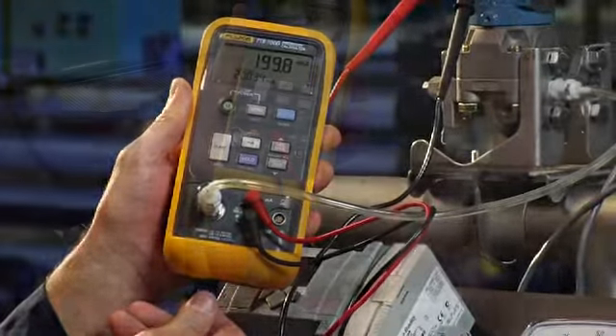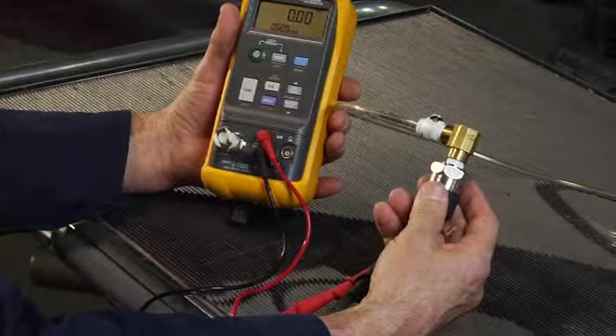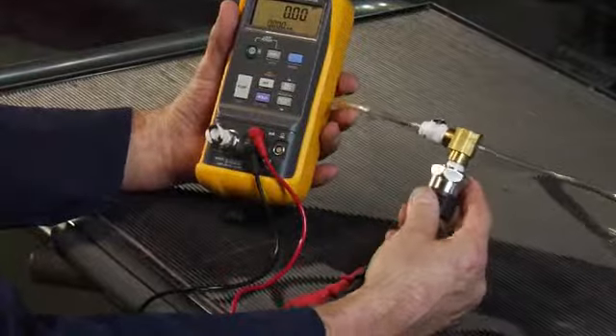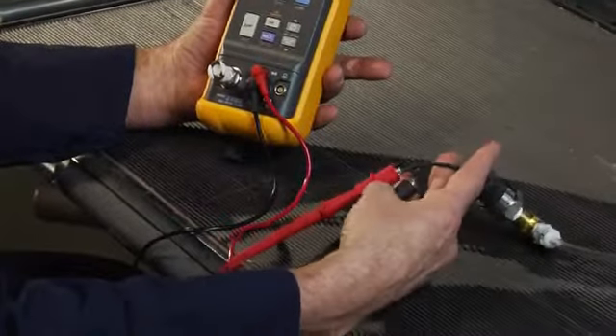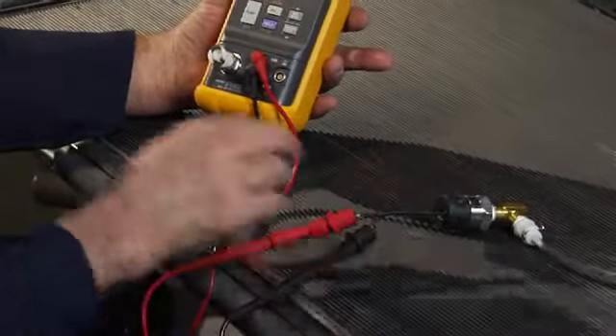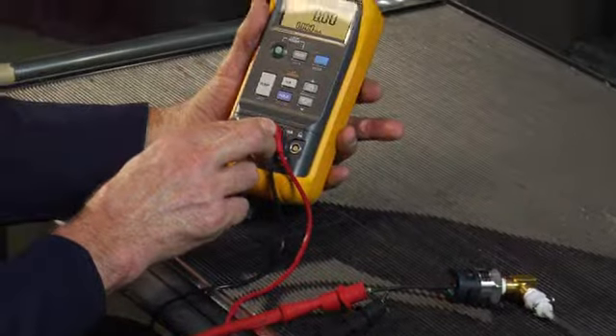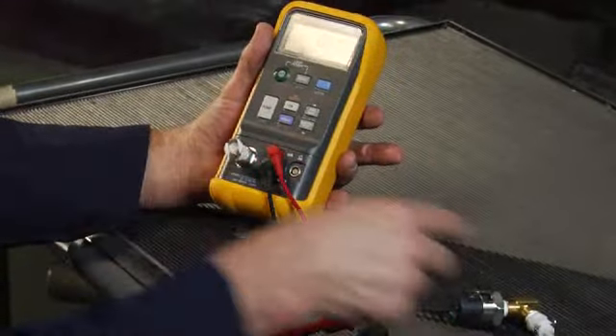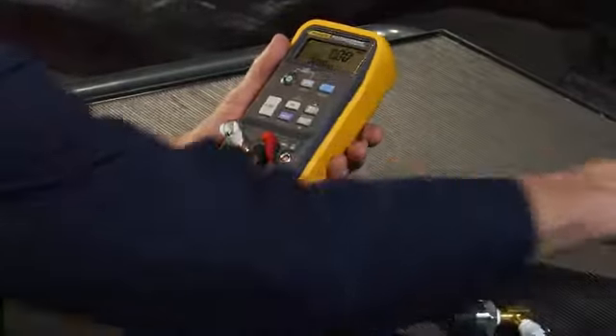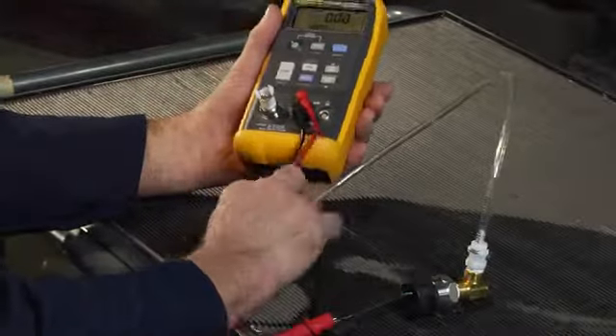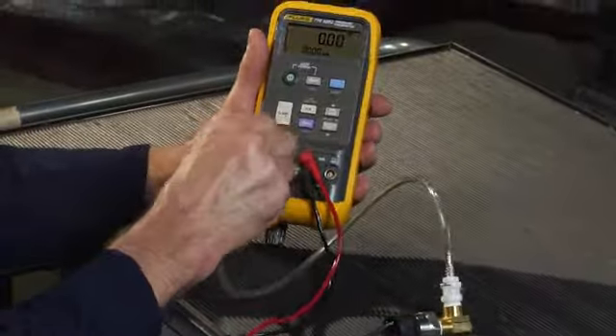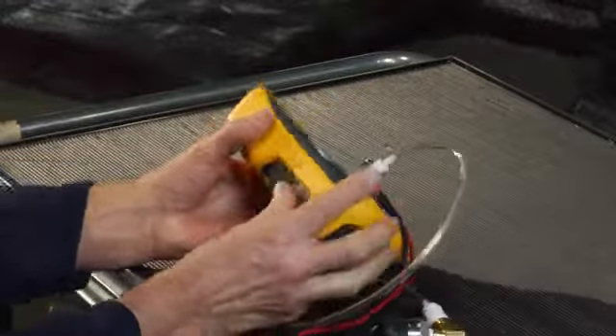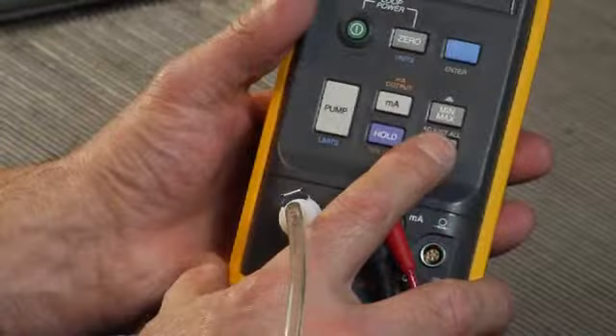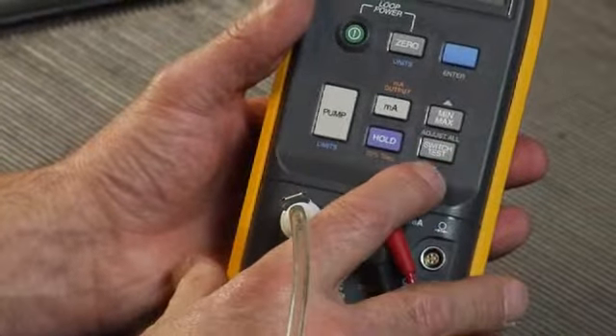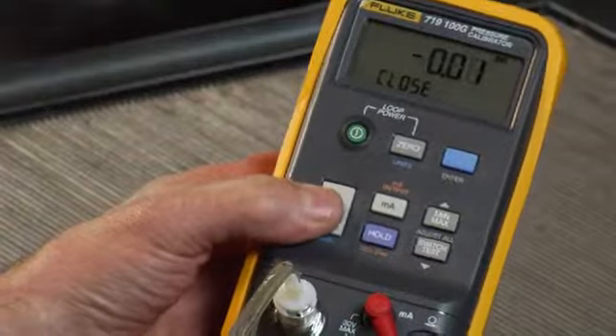of the transmitter. In this example, we're going to test a pressure switch by measuring the de-energized contacts of the switch with the 719 while applying pressure to the input of the switch from the output of the 719. This switch has a set point of about 10 psi. Connect the pressure and verify that the vent controls are in the closed position and set for positive pressure. Enter the switch test mode. Switch state initially is closed.